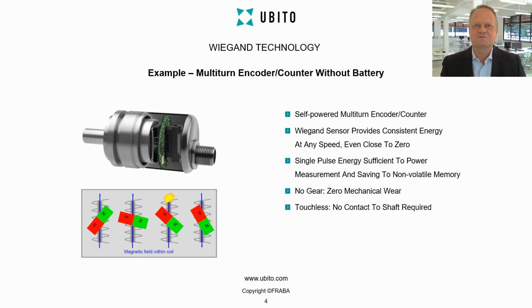At a certain threshold, reached at a certain angle, this potential energy becomes so high that the field inside the Wiegand sensor suddenly flips from up to down, generating the electrical pulse that we need. With the power from this single pulse, we can boot the electronics, do the measurement, counting, and save the result into non-volatile memory. We also use the timing and information from this pulse for synchronization of single-turn and multi-turn. As this is a non-contact principle, it also helped us design encoders that are much more robust - they can be perfectly sealed and there's zero mechanical wear.